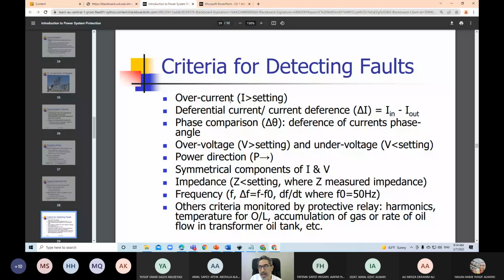If the voltage exceeds 110% of the rated voltage, this is an overvoltage, and if this persists for a certain duration of time, then we take action. This is overvoltage protection. Or the voltage is below 90% of the rated voltage. That's an undervoltage situation, and we can take action. We can detect reverse power, as I mentioned before. So we measure the power and see if the power direction has reversed. We can detect faults based on symmetrical components.